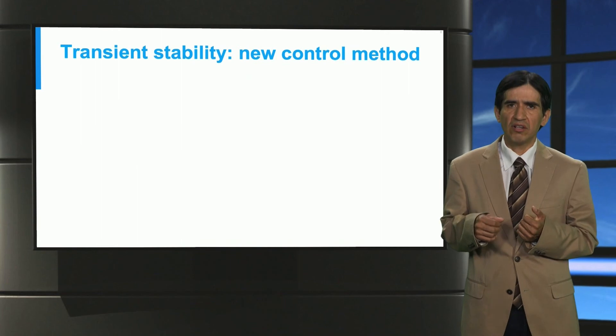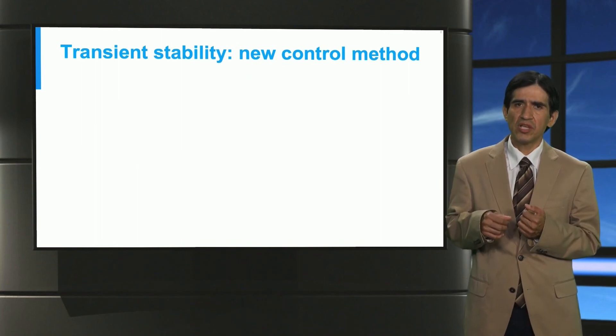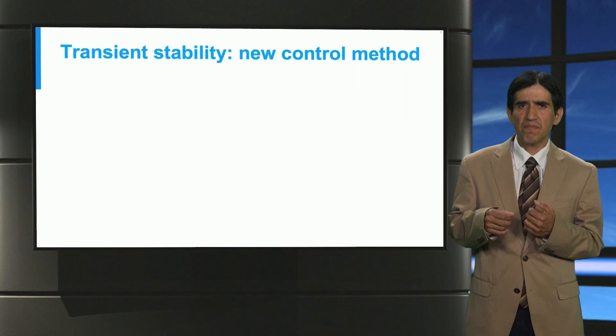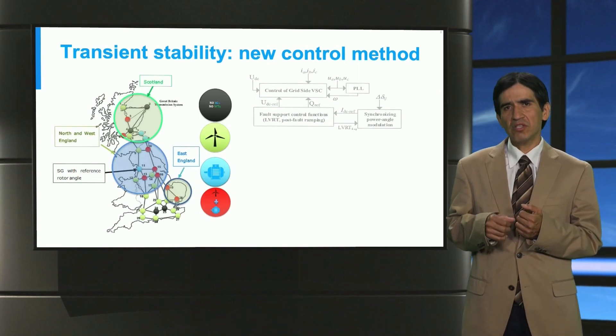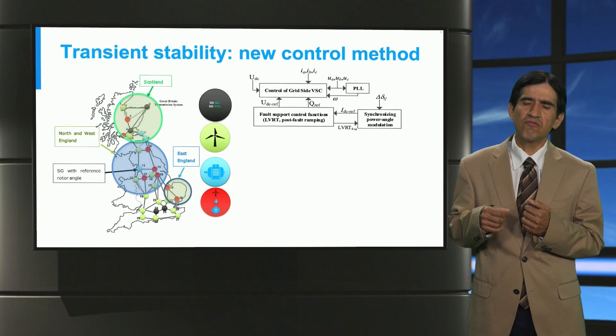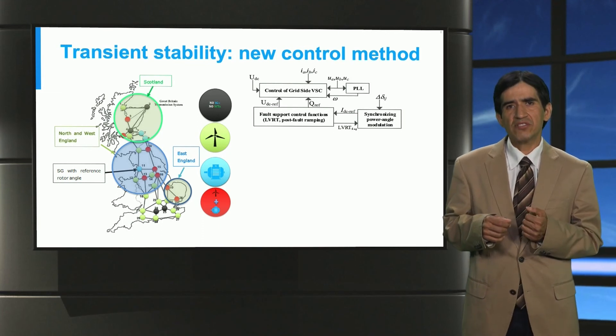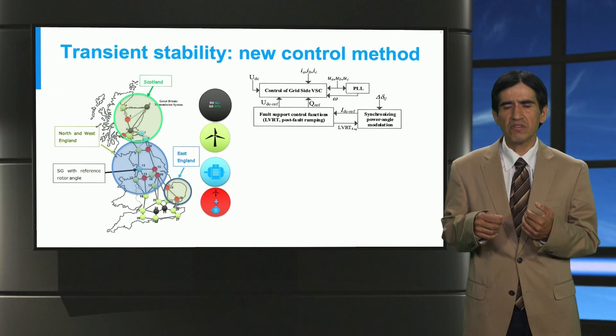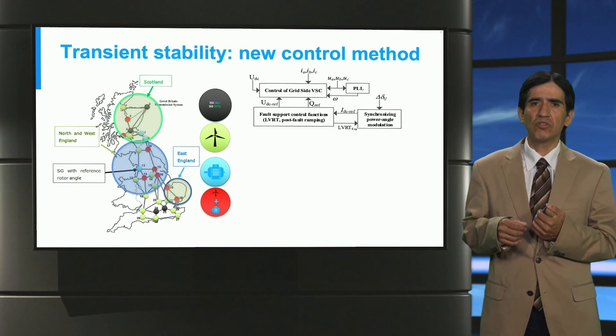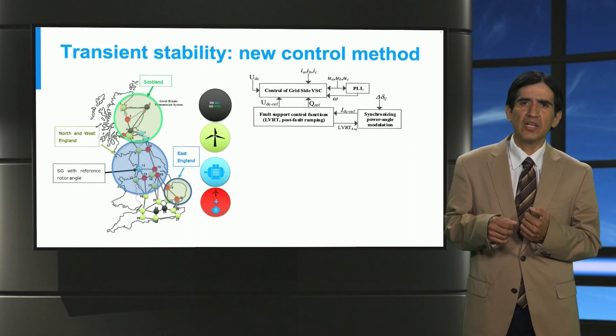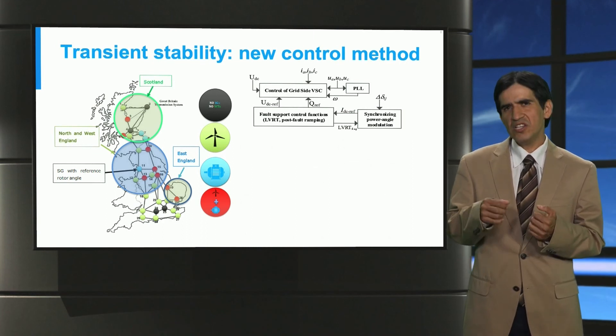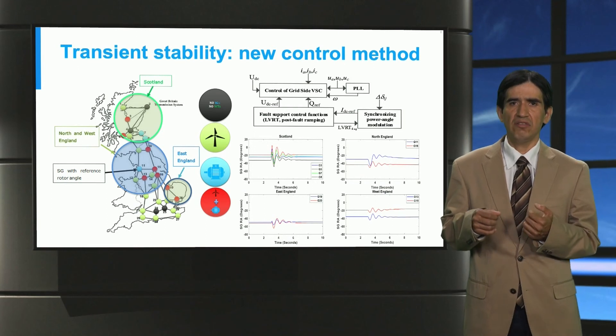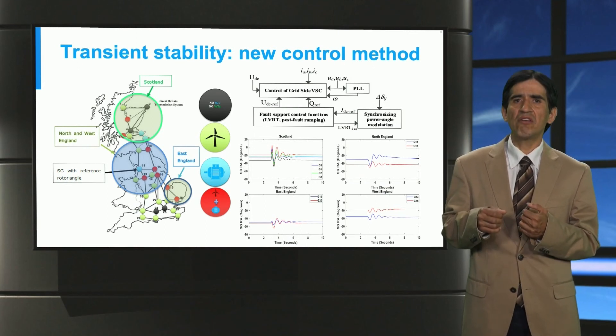Another example upgrade of control systems needed for secure operation is the control method for transient stability. In this second example, it concerns synchronizing power angle modulation. This method is superimposed on the fault support control functions of a grid side converter. Based on measuring relative angle deviations between remaining generators in the system and high shares of renewables, the method helps in reducing the magnitude of the rotor angle swings while supporting a quick decay of these swings. In this way, the disconnection of synchronous generators is prevented, safeguarding the system operation from cascading outages, which can lead to undesirable power disruptions.